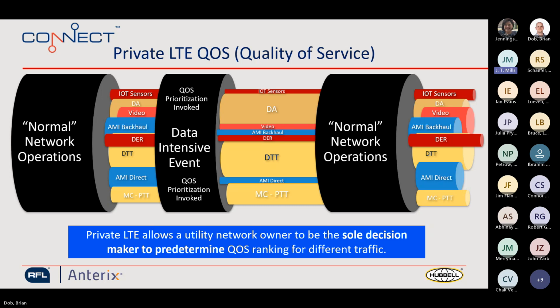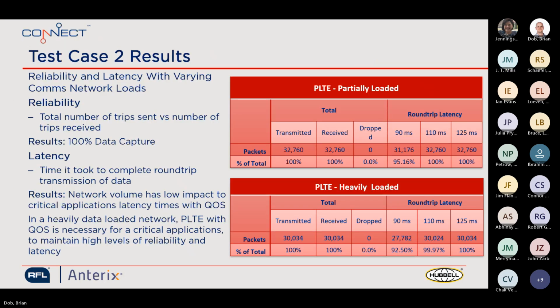So you, during that event, can control what information I get, how fast I'm getting it during any of those events. So think of it as ranking, right? 1, 2, 3, 4, 5, 6, 7, 8. You're able to get your priority 1 first, and the system maintains that data 100%, and it gives it the low latency. But priority 8 becomes the last thing in the queue. But you're able to shape that data and shape that data path as you, the utility, the end user, deem fit. All right, next slide, Brian.